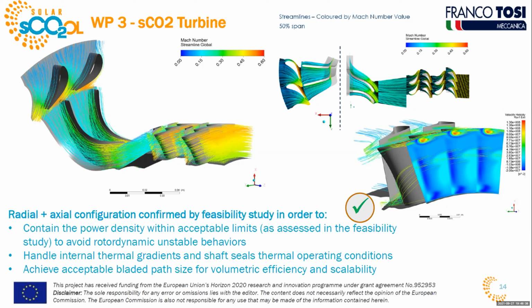Some specific methods have to be established, since usual norms and criteria are not suited for this kind of machine. The extremely small size of this machinery brings us to handle internal thermal gradients and shaft seals, typically dry gas seals, with thermal operating conditions that can be extremely severe. It's also mandatory to achieve acceptable blade path size for sufficient volumetric efficiency and scalability, so as to avoid designing the next commercial machinery in a completely different way from what we've done here.